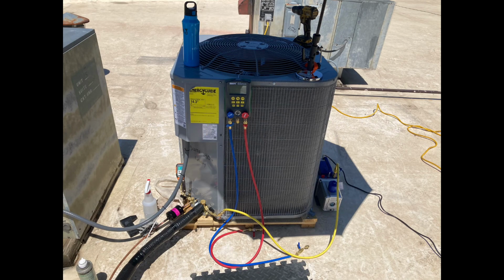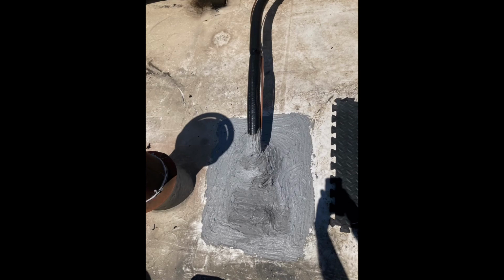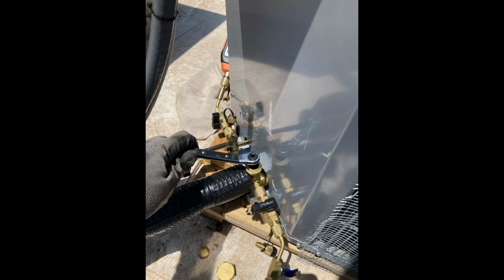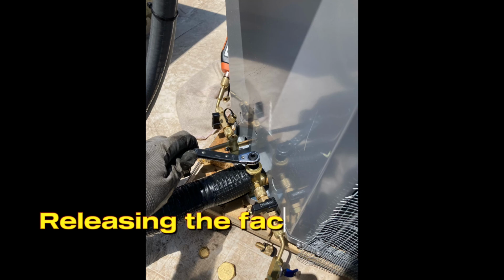Now we move on to pulling the vacuum on the new line set and A coil. So I'll hook up my vacuum pump and hoses and vacuum gauge. And while we're waiting for the vacuum to pull down at or below 500 microns, again, ideally as low as you can go with your vacuum pump, I went ahead and resealed up that roof penetration to make it weatherproof. So we successfully held a vacuum. We're going to go ahead and open the service valves now with our service wrench on both sides.